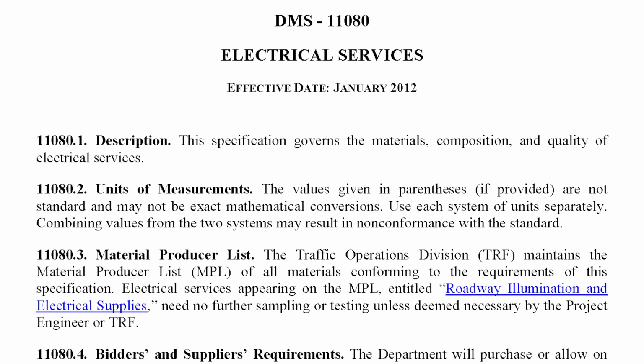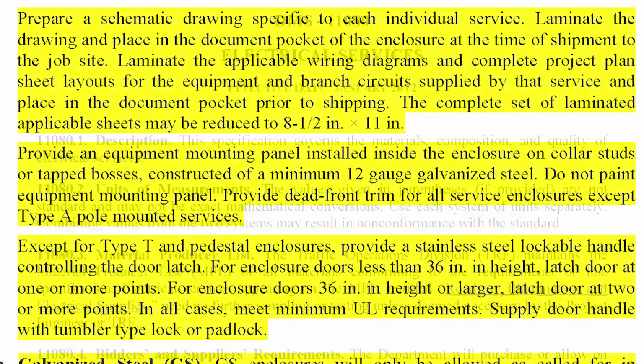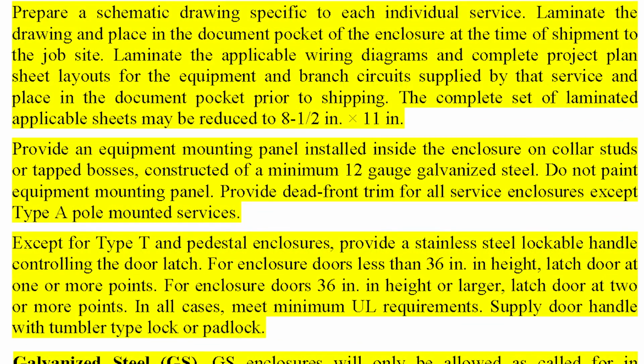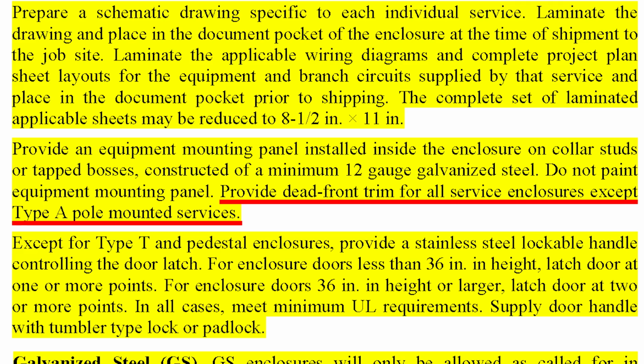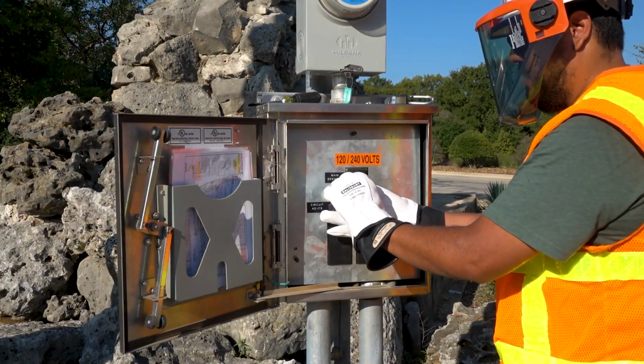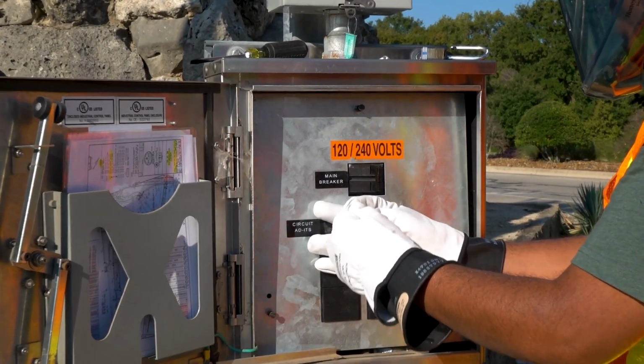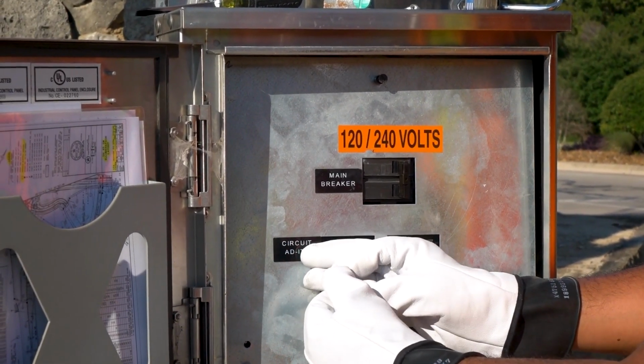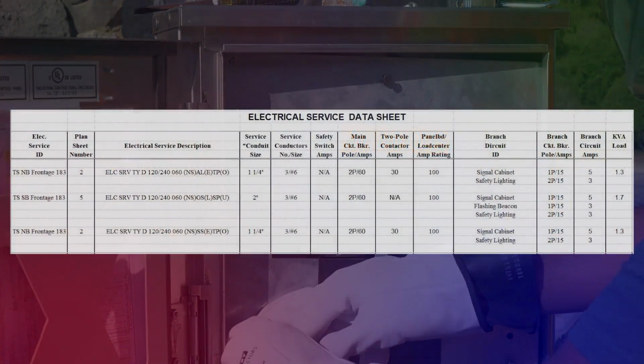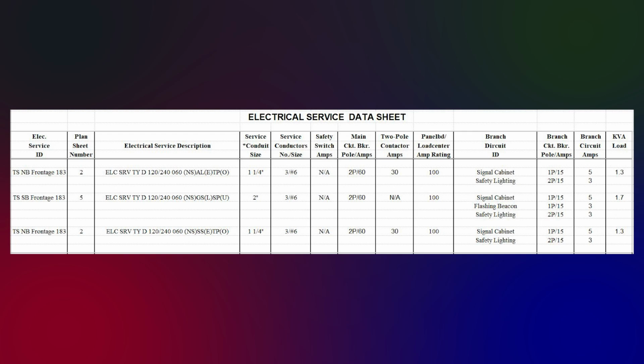As stated in TxDOT's Departmental Material Specification DMS 11080, all enclosures except Type A pole-mounted service enclosures must have a dead front trim properly installed. The inspector should confirm that this specification is met. A dead front cover is a feature on many pieces of electrical equipment. A dead front ensures that personnel do not accidentally contact potentially deadly electrical components. The inspector will need to look at the electrical service data chart in the plan set to determine the physical size and type of material for each service.